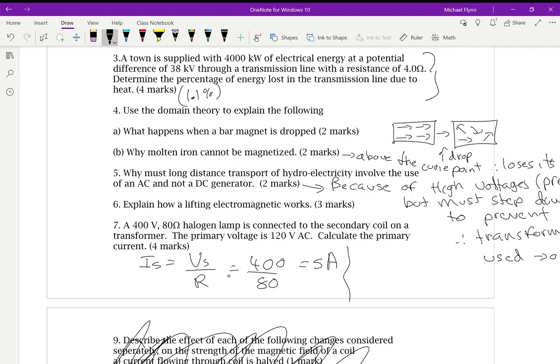The primary current, it'll be Ip over Is equals Vs over Vp. So, just solving for Ip you're going to get 400, we're doing that right? Yeah, I'm doing that right. So, it's going to be 400 divided by 120, and then I'm going to multiply that times 5. I get 16.7 amps. There you go. That's your answer.